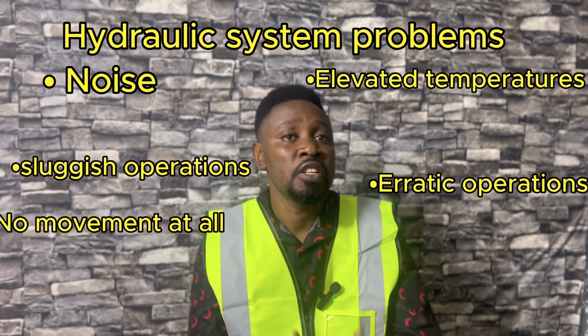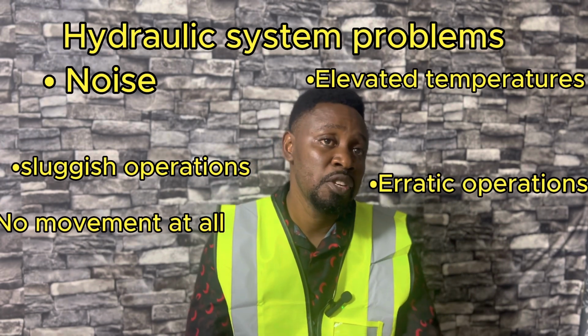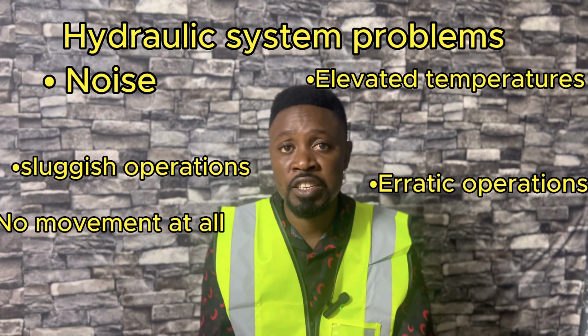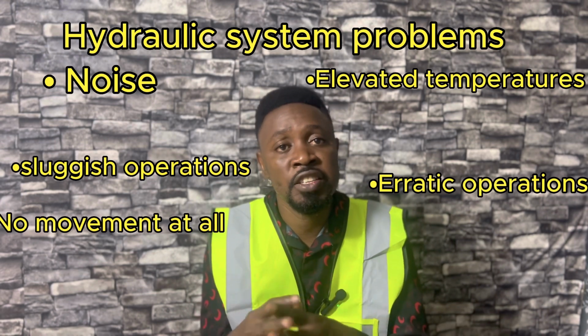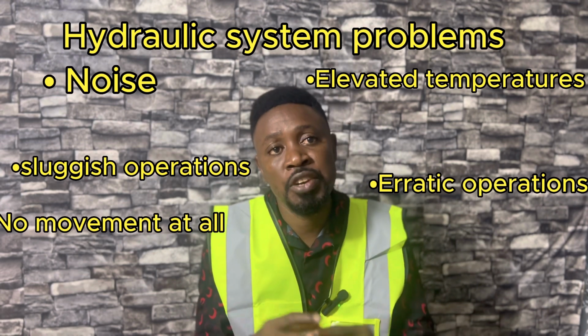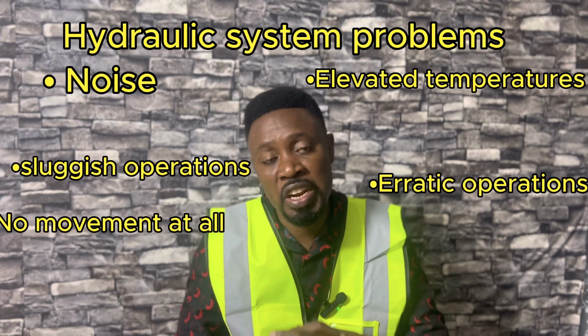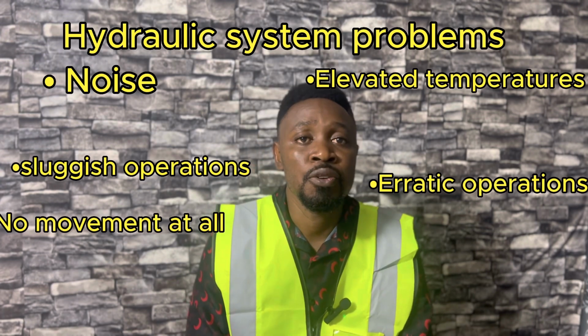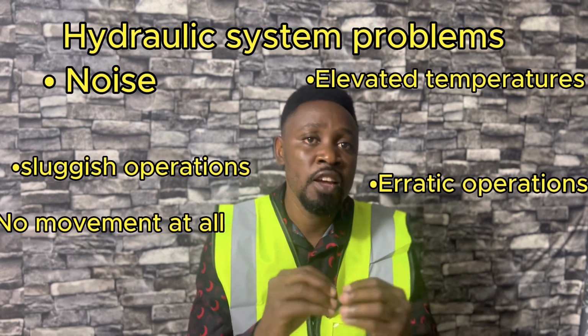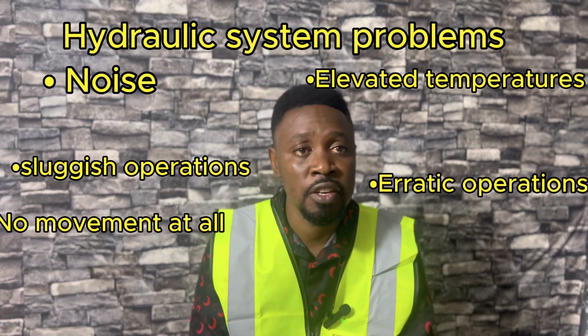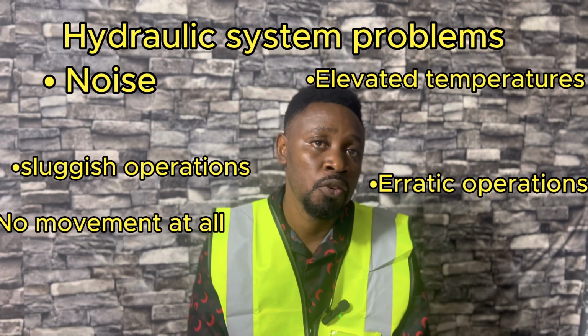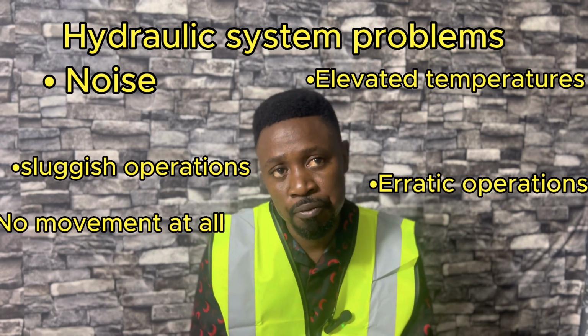So, in eliminating them, you make sure the system is properly sealed. When flanges are removed or parts are changed, they are properly fixed and the system is properly bled to ensure that no air leakage occurs in the system as the machine or the pump operates.